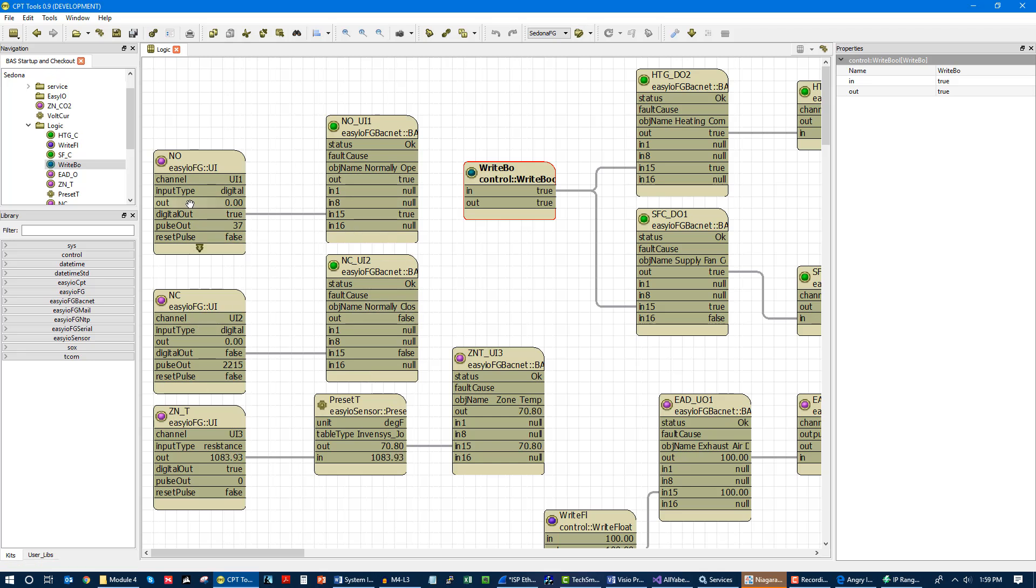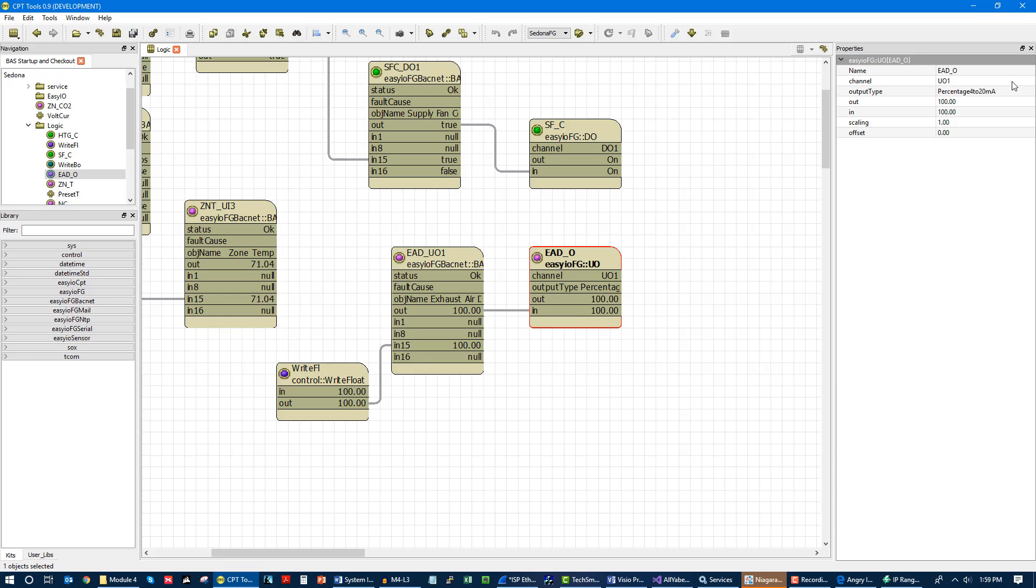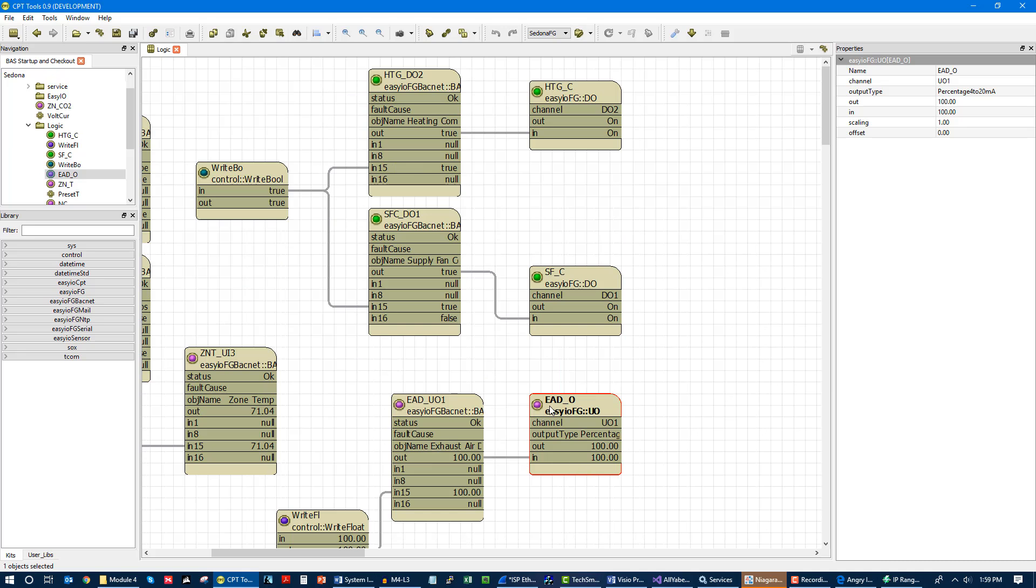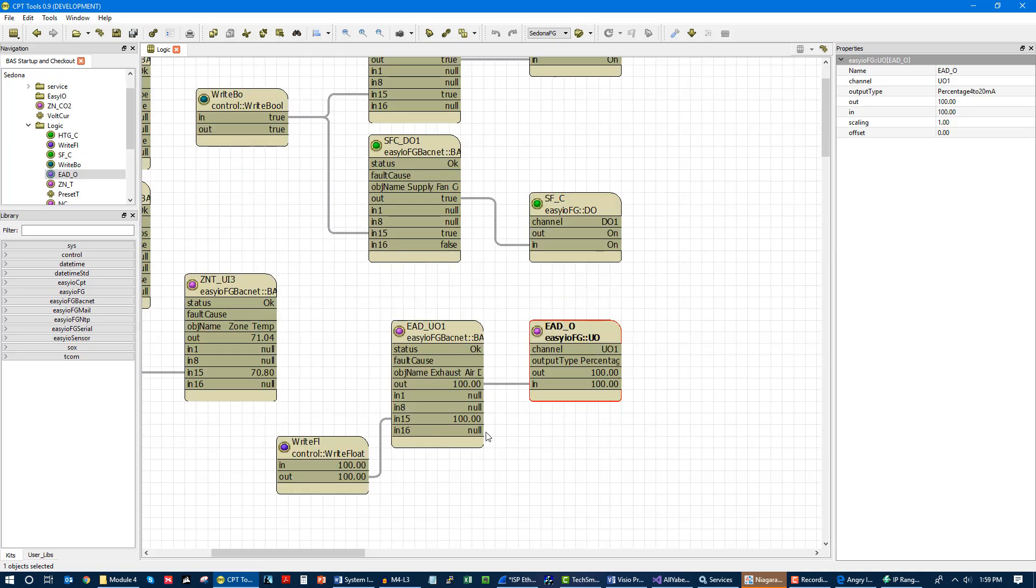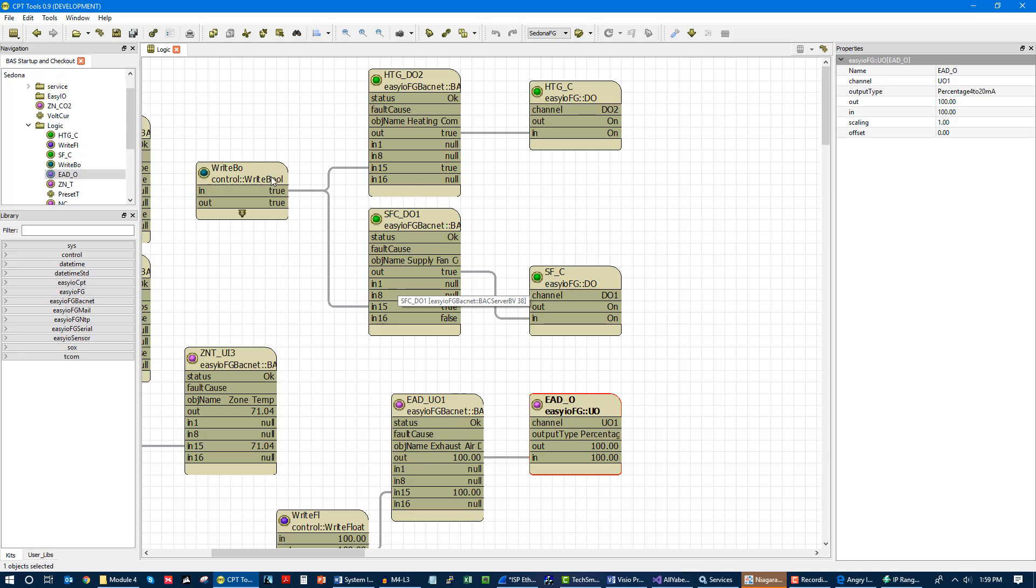When I actually change its state, we are seeing that state change reflected in inputs. We see our digital inputs and we see our zone temp right here. Then we can see I also have a universal output that I'm running as a zero to 10 volt output. This output right here is going and driving zero to 10 volts to the output and is causing that actuator to change state because this is actually connected to an actuator. Then you can see these little BACnet points right here that are interrupting my outputs. This is passing through here and you can see me writing to a priority array. The heating command is once again passing through this priority array.